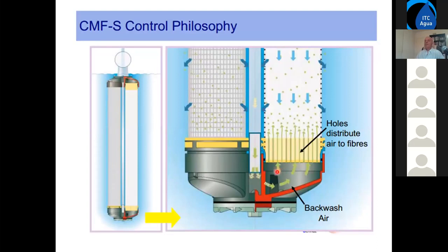So in the membrane filtration, as in differentiating to the RO, there is still very little standardization. So every membrane manufacturer have a different configuration. Therefore, the membrane cannot be replaced from one manufacturer to another. I mean, they can, but then you have to change the train completely. Frequently, you have to change the pumps because there's different flow rates, both for the feed, backwash, and air scouring.